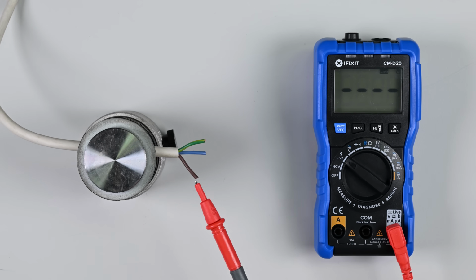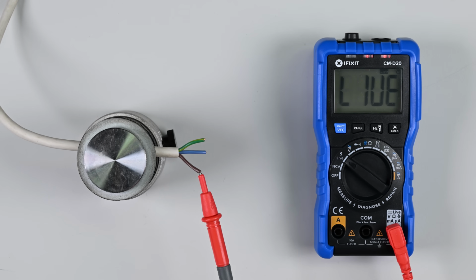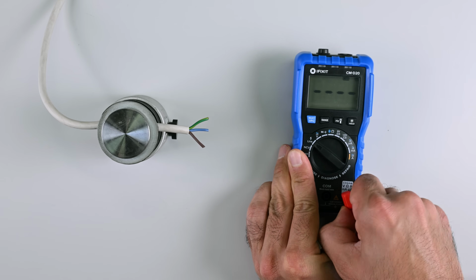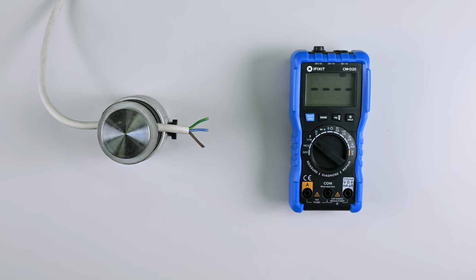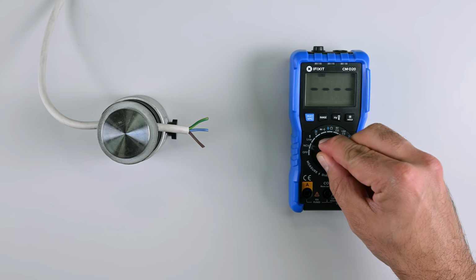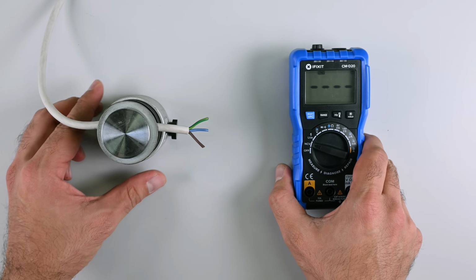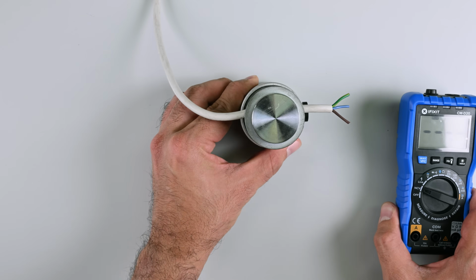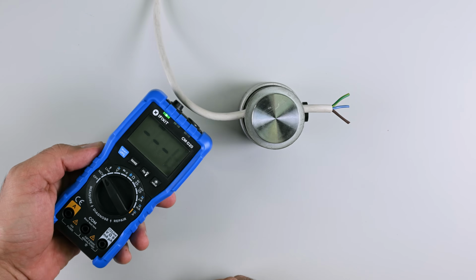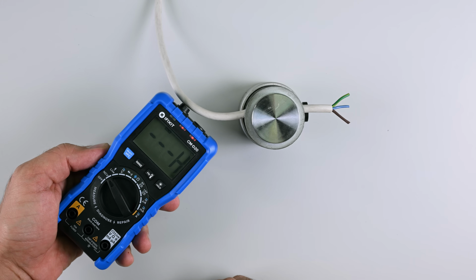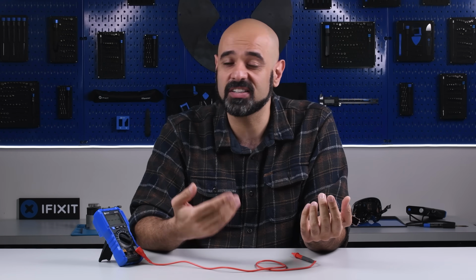The next setting on the multimeter is live, which is used to check for AC voltage in live wires using a single probe. For this test, we'll need to connect one of our probes to the terminal on the right, also labeled live. Unlike the NCV measurement, the live test allows us to check for voltage in a single wire within a larger clump of wires. Bear in mind it's always prudent to confirm test results by other means. Use the NCV function in conjunction with the live test mode to confirm that a wire is safe to handle whenever possible. Both these tests are great ways to see if a light switch or a wall socket are energized.